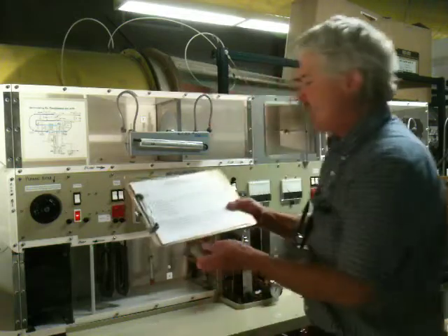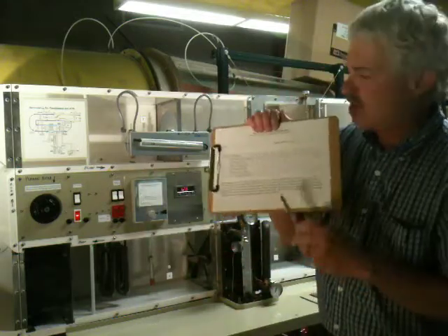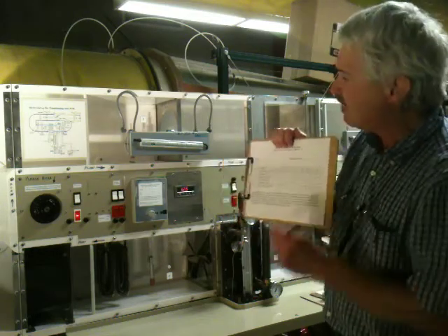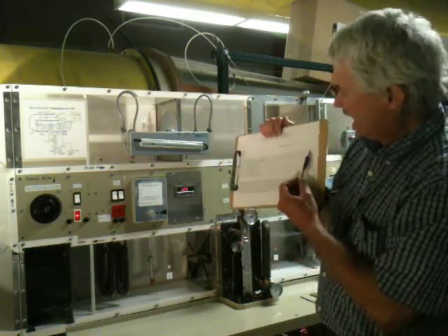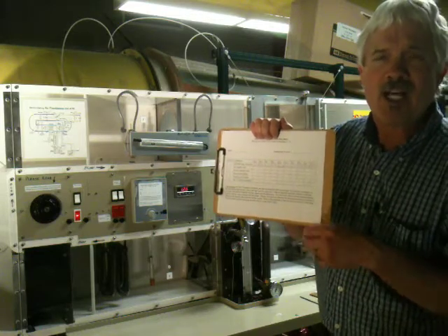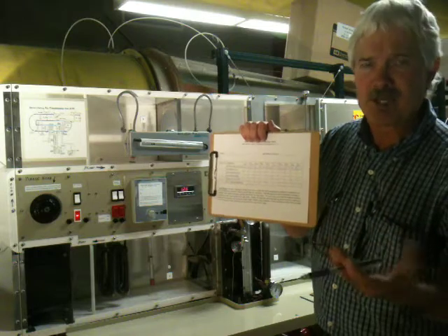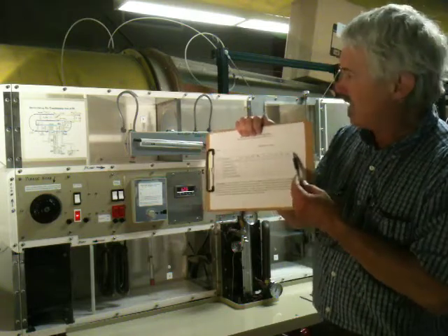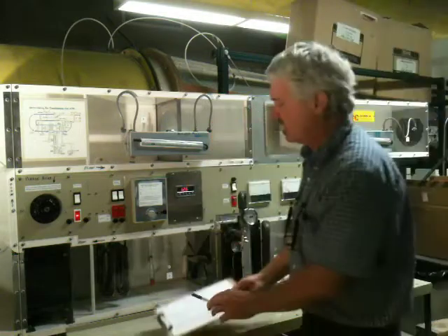For example, we would expect all the dry bulbs and wet bulbs to be identical because we're not doing anything else really, except that between D and E we are going through the fan. The fan has an electric motor that will heat up the air slightly, so that's one possible explanation for the temperature readings at E being slightly higher. Most of the rest of the lab, the differences in temperature readings will be due to the other operations that we're performing.